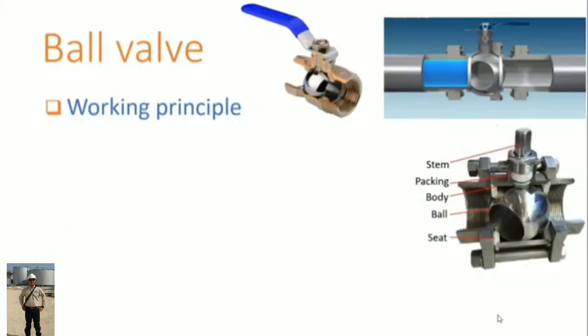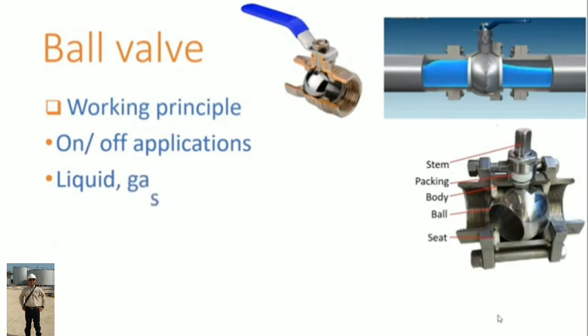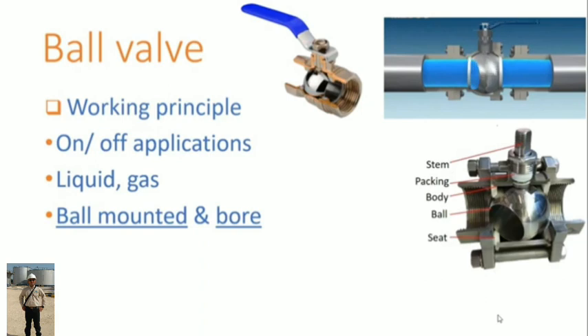Working principle of ball valve is very similar to plug valve. The seat matching the ball is circular, so seating stress is circumferentially uniform. The seats are usually made by polytetrafluoroethylene, which is inert to all chemicals and has low coefficient of friction. The valve uses only for on-off applications dealing with both liquid and gases. Ball valve can be divided into several types according to the way of ball mounted and bore type.